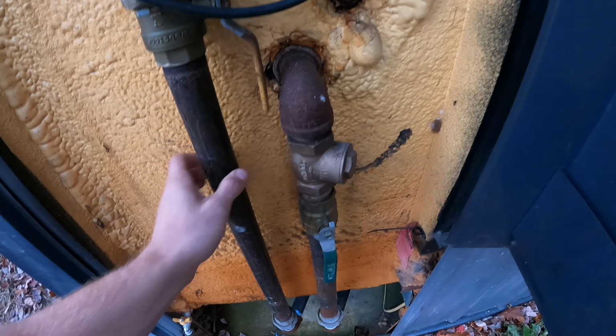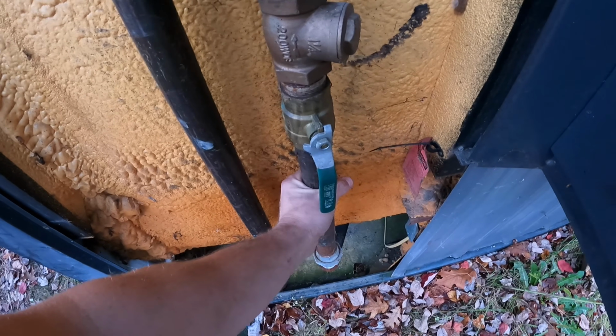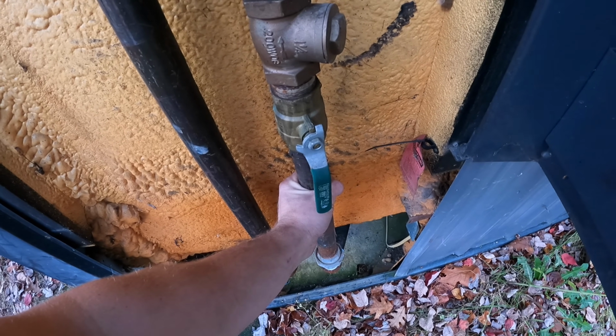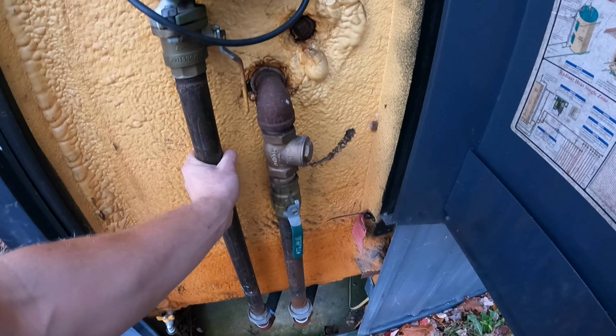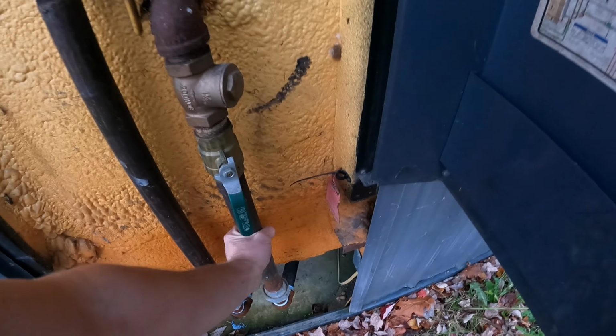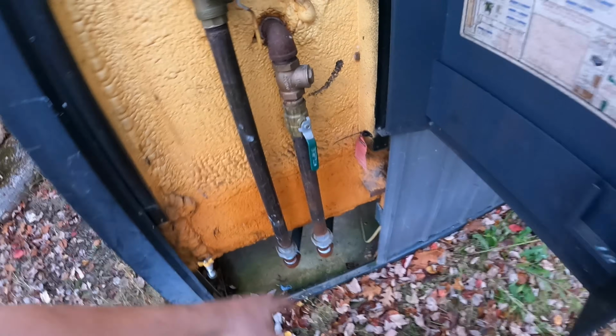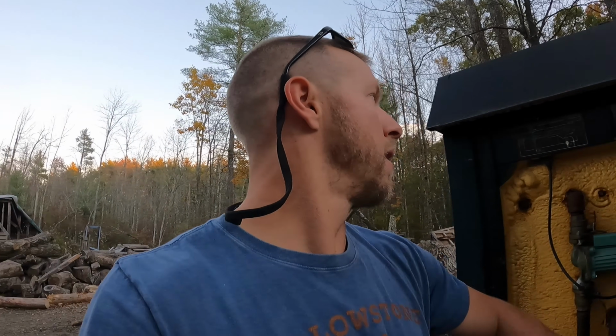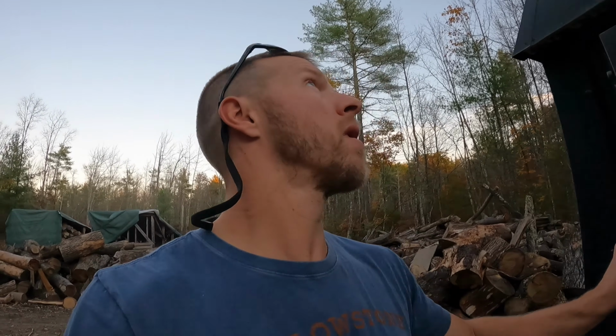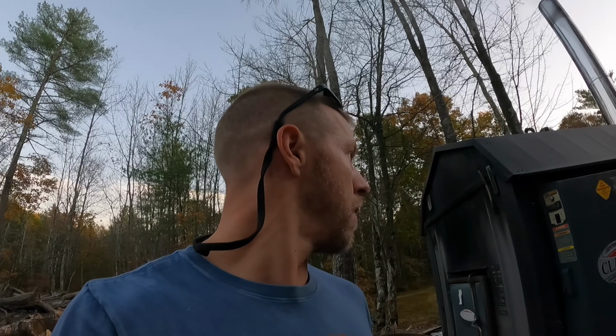That don't take long to get hot. So this is the cold water return. Right now we're pumping all the cold water that was underground and in the house system. It won't take long, by the time I get back into the house this pipe's going to be hot. It's circulating, it's not calling for heat. 192 degrees, we're good to turn on that heat exchanger pump.